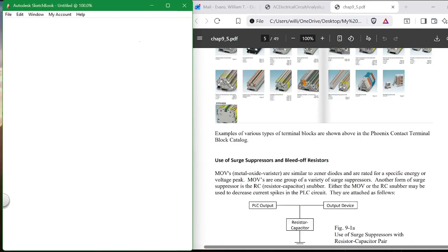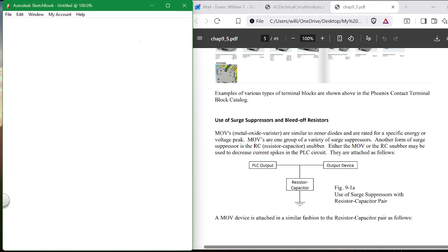I don't want to get into this in depth, but you can have a situation where an output turning on an input causes the input to always be on. The simple reason is because most outputs have leakage current in them. If they're solid state, they have leakage current, and some inputs will detect that leakage current and actually turn on because of it. So that bleed off resistor is sometimes necessary to alleviate that. Not always, but sometimes. You have to be careful.